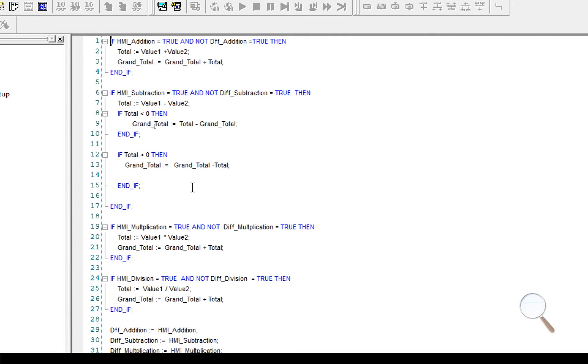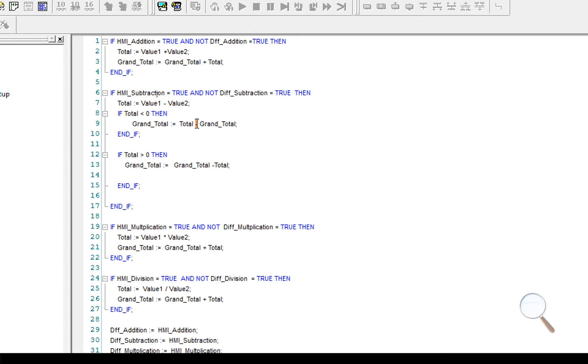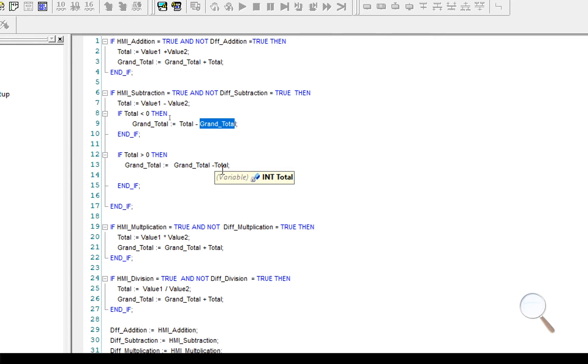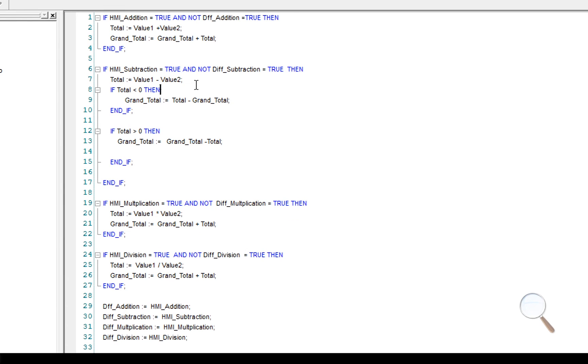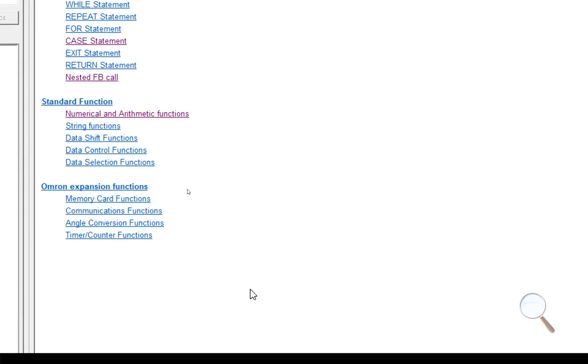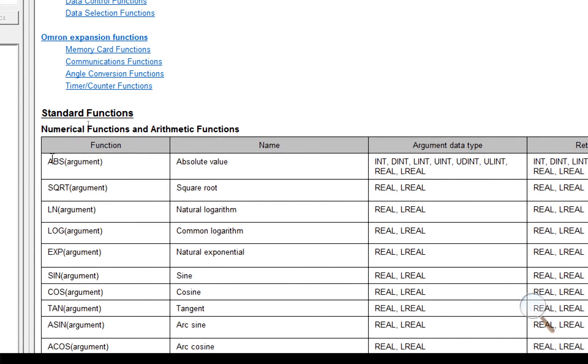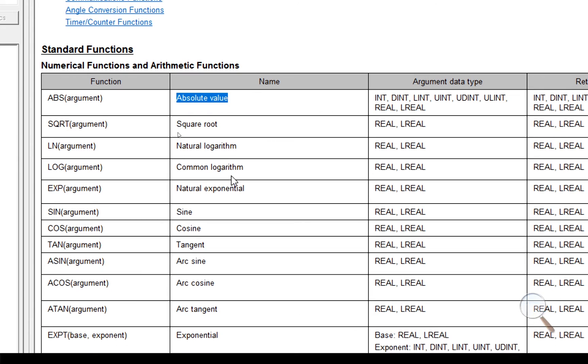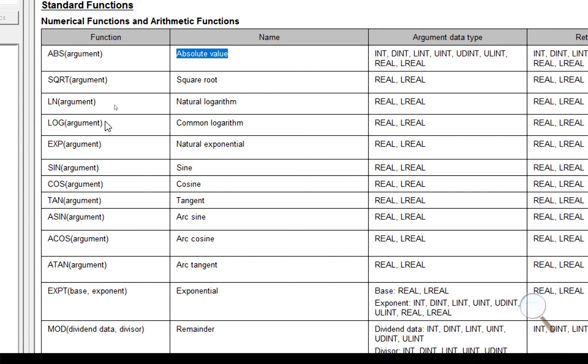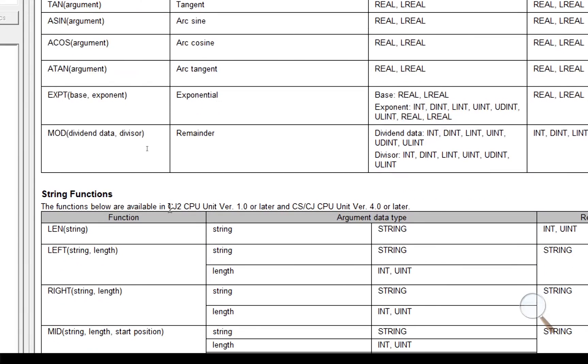Back in CX Programmer, you need to look at what we actually asked it to do. Putting the minus in here is not the same as using the numeric function within the ladder logic. That minus there makes this entire variable a minus, like it would do in maths. So what we need to do is use a different function. But what function can we use? Let's have a quick look at the Structured Text Help by right-clicking, go on Structured Help, and we can have a look at the numeric functions. The first function it gives us is abs, our absolute value. So that will give me the absolute value and that will sort out my issue with the minus sign. So let's use that instead. Just for completion, we also have a square root, we have the natural log, we can do the sine, cos tan, arc. We can work out remainders. All this is within the function set.